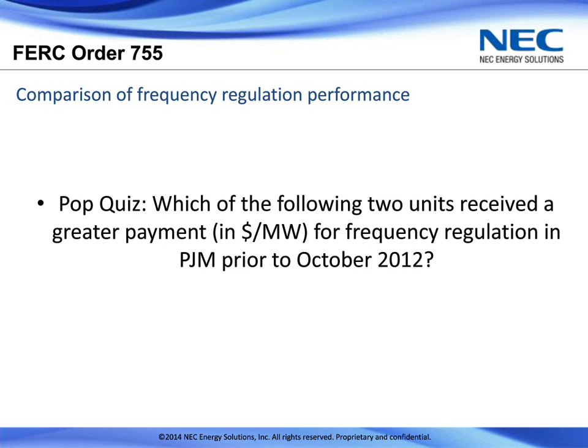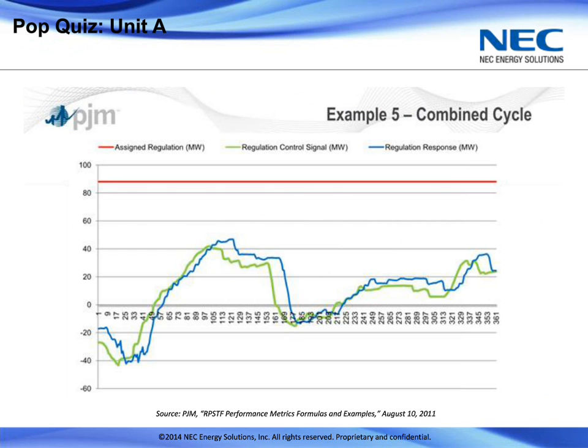I'll show you two different resources providing frequency regulation and how well they're doing it. This first example is a combined cycle turbine. The green line represents the regulation control signal the ISO, PJM, provides to the generators, and the blue line is the response to that signal. The turbine tries to follow the control signal as closely as possible, and as you can see, it does fairly well, with just a little lag and accuracy difference.